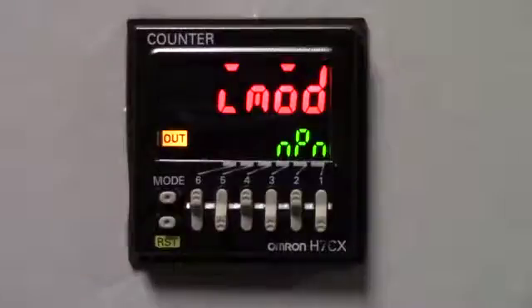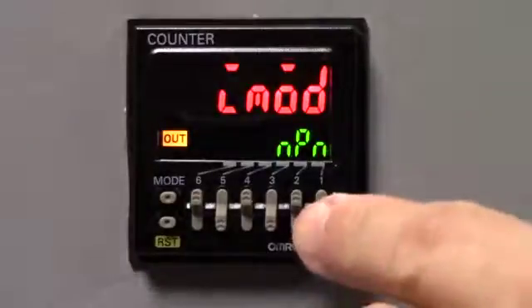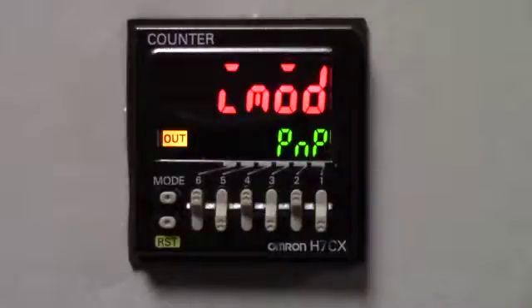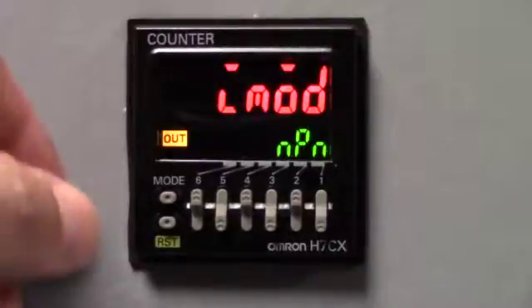Next is our input, IMOD. This function here, this dictates to us what function mode will be needed for the input, NPN or PNP. Now, if you're using a basic switch or a push button or a limit switch, you could keep it on the NPN. And obviously, if you have a PNP input, you would press the number one key. And then that will allow you to accept a PNP input into the counter. Seeing how we're using a push button, we're going to keep it at NPN. So next, we're going to press the mode key to advance to the next function.